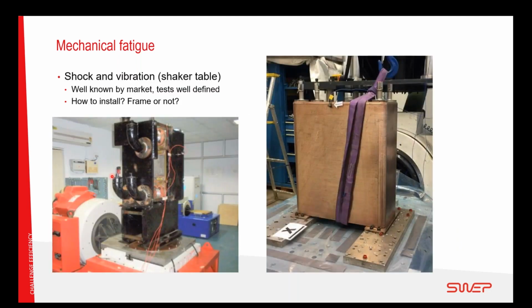Another part of the mechanical fatigue testing is this shock and vibration testing, shaker table testing. It's a test that's very well known by the market. The tests are well defined because, for example, all auto car manufacturers have their own designed tests. The question that we often run into is, how is the heat exchanger actually installed? If you look, for example, at the picture on the left, you see a heat exchanger fully rigid mounted into a frame. So actually, when you're testing this on a shaker table, you're testing the frame more than the heat exchanger itself.